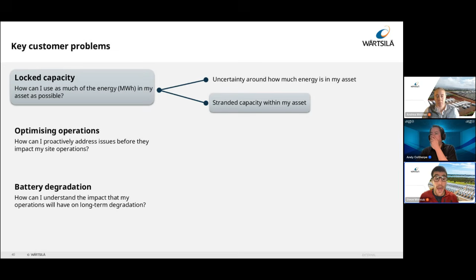One approach that many folks take, and that we take at Wärtsilä as well, is SoC calibration. We use an SoC calibration algorithm where we automatically calibrate each system on a rolling basis. So if you have 100 battery systems or inverters at a site, we'll automatically cycle through those on a rolling basis so each one gets calibrated, let's say, every 2 weeks. When that calibration happens, the SoC is reset to its most accurate possible level, and a balancing plan takes place so the imbalance of the system can be reduced. We do this in a way that doesn't impact the maximum power output of the site.